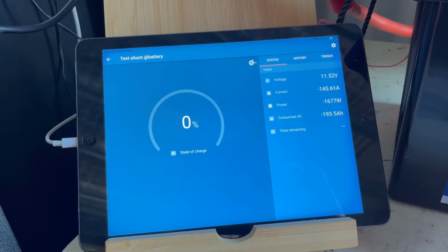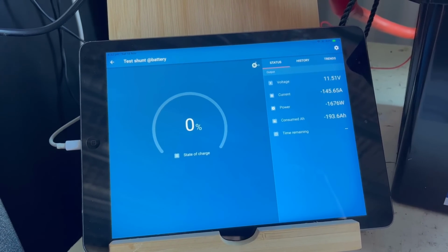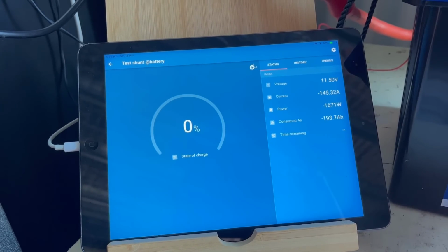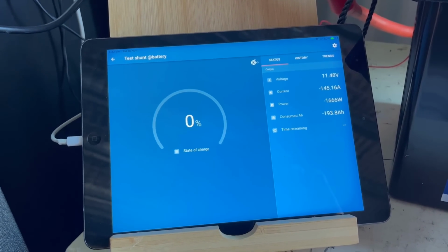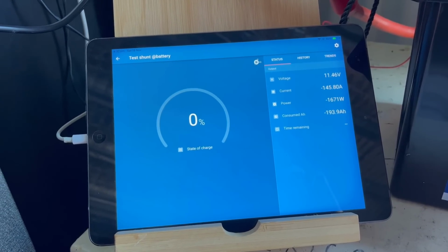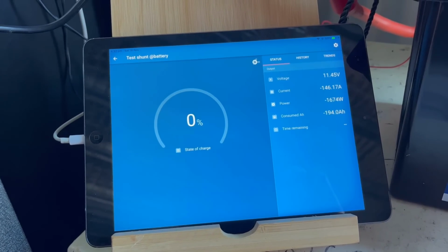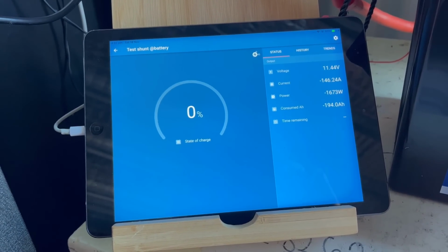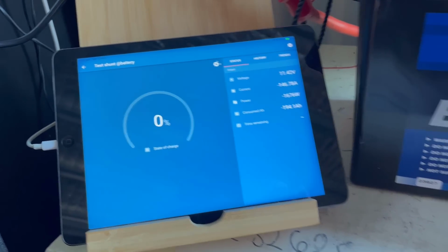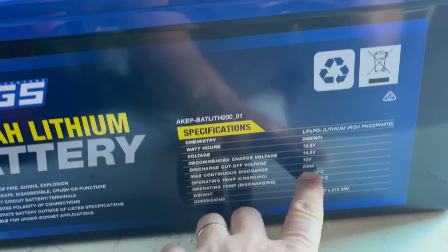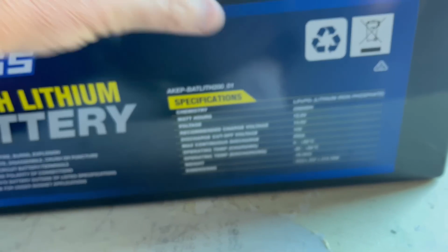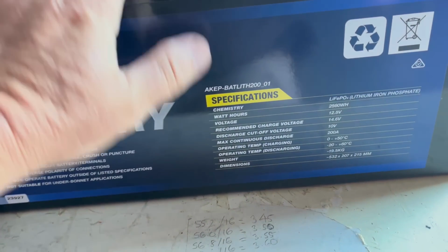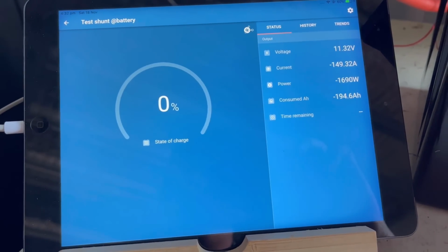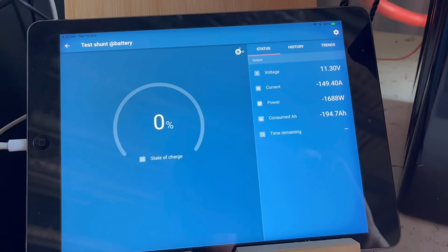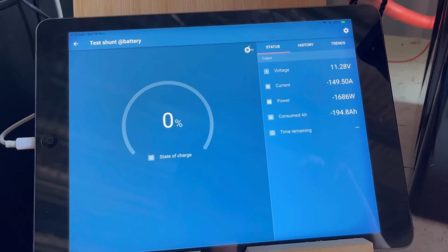We're pulling 145 amps out of this battery. Obviously the amps go up as the voltage comes down, but in the real world, are you going to pull that sort of amperage out of this battery continuous? No, you probably won't. But it is a 1C rated battery, so continuous discharge of 200 amps, and it's a 200 amp hour battery, so we're not doing anything wrong. We're actually way under spec of what it's supposed to be able to do. So it should pull 200 amp hours.